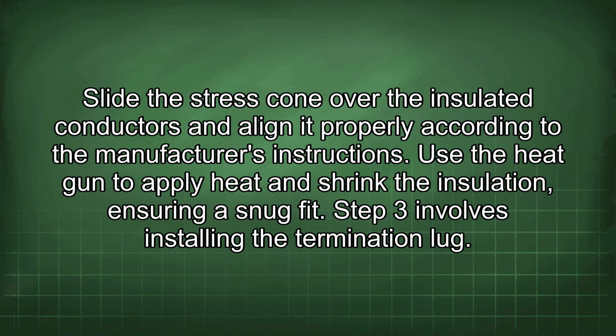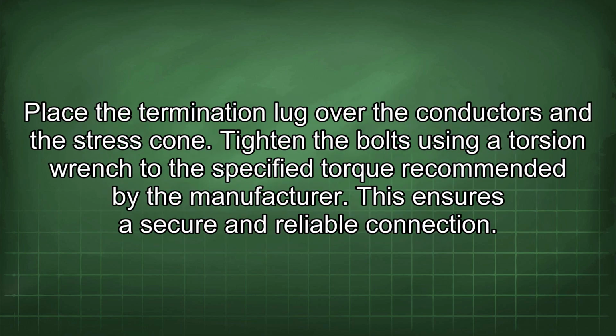Step 3 involves installing the termination lug. Place the termination lug over the conductors and the stress cone. Tighten the bolts using a torsion wrench to the specified torque recommended by the manufacturer. This ensures a secure and reliable connection.